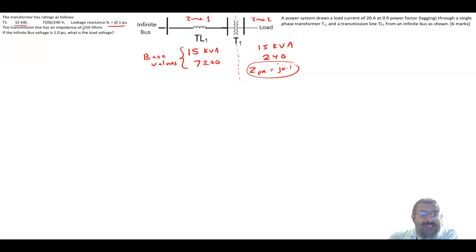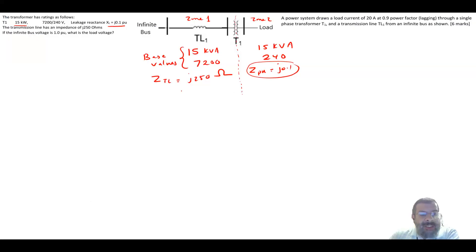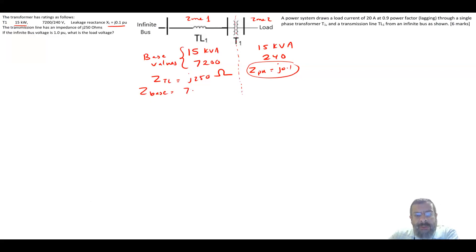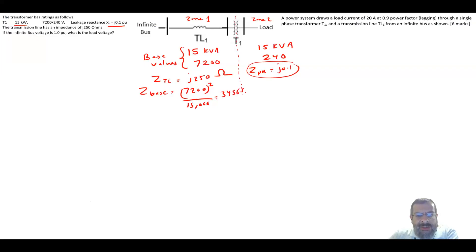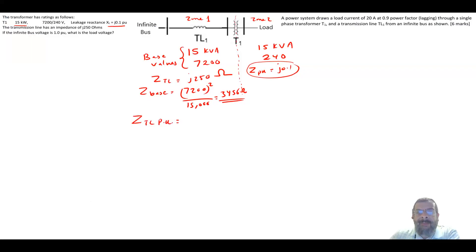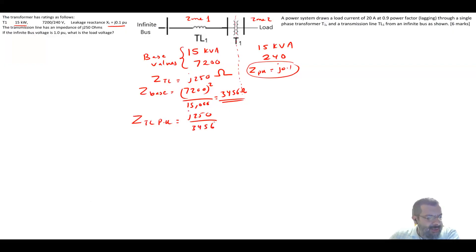The transmission line impedance is j250 ohms and must be converted to per unit. We find Z base in zone one: Z_base = 7200² / 15000 = 3456 Ω. Therefore, Z_transmission_line in per unit = j250 / 3456 = j0.0723 per unit.